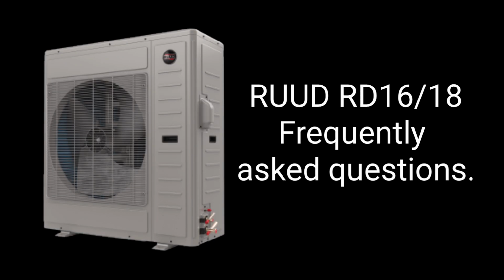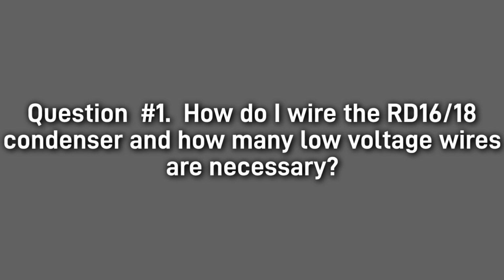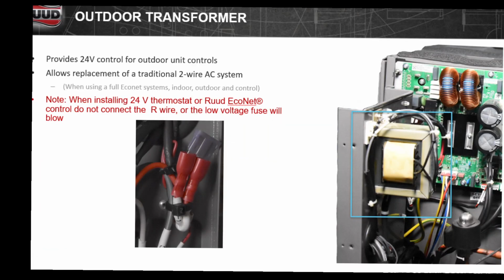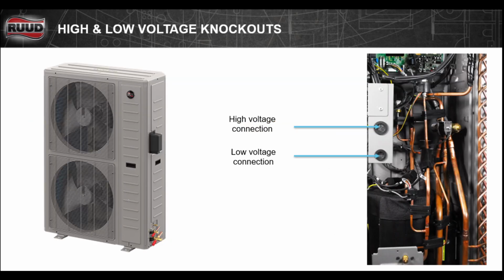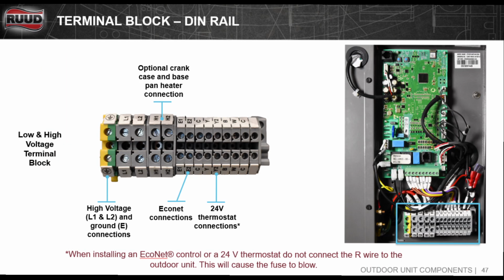The Ruud RD16 and RD18 frequently asked questions. Question number 1. How do I wire the RD16 and RD18 condenser, and how many low voltage wires are necessary? The RD16 and RD18 condensing units have a built-in 24 volt transformer, so we never want to connect red or else we will blow the built-in fuse. Remove the side panel and utilize the high voltage and low voltage connection points.